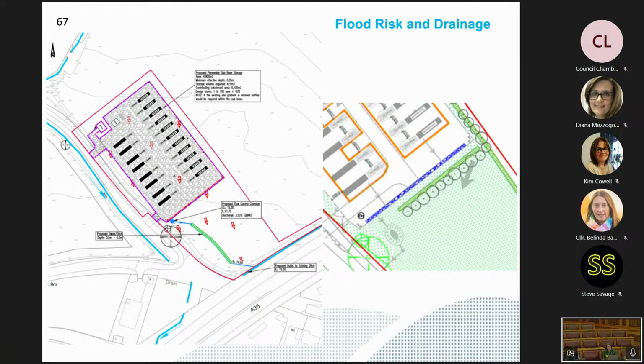The majority of the surface surrounding the battery storage is proposed to be constructed from permeable materials. However, the battery units, associated transformers, units and substation will produce some additional runoff. The proposed SUDS for the site include a combination of permeable paving, a trench, and an attenuation basin, designed to provide the required storage volume to retain a 1 in 100 plus 50% climate change event.